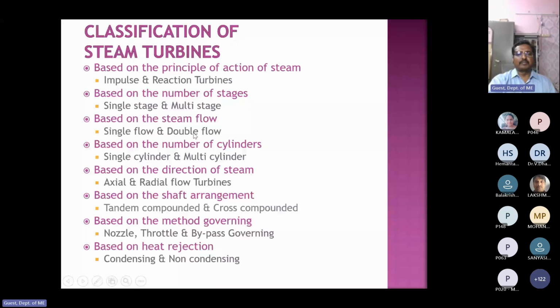But power utility plants are of axial flow type. Based on the shaft arrangement, there are tandem compounding and cross compounding. Here compounding means something different from what we learned in another way, like pressure compounding and velocity compounding. This compounding is with regard to the joining of the shaft.